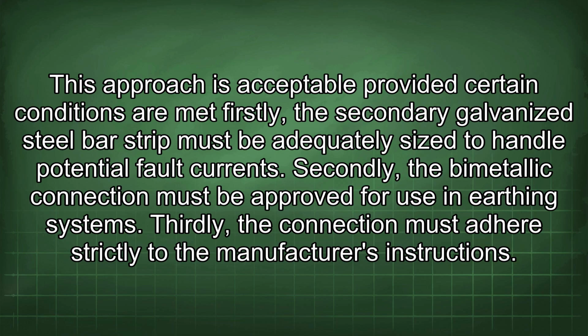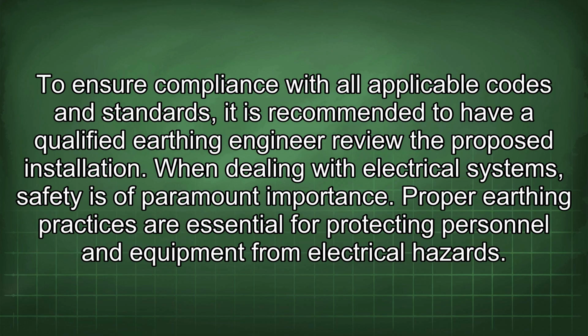Firstly, the secondary galvanized steel bar strip must be adequately sized to handle potential fault currents. Secondly, the bimetallic connection must be approved for use in earthing systems. Thirdly, the connection must adhere strictly to the manufacturer's instructions. To ensure compliance with all applicable codes and standards, it is recommended to have a qualified earthing engineer review the proposed installation. When dealing with electrical systems, safety is of paramount importance.